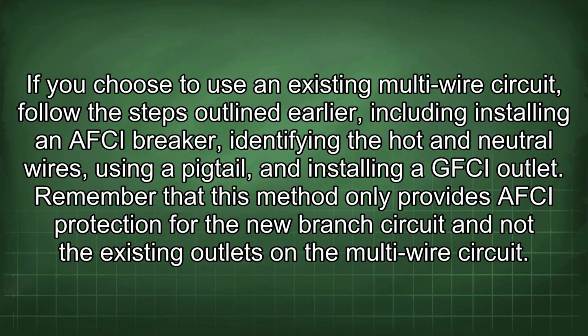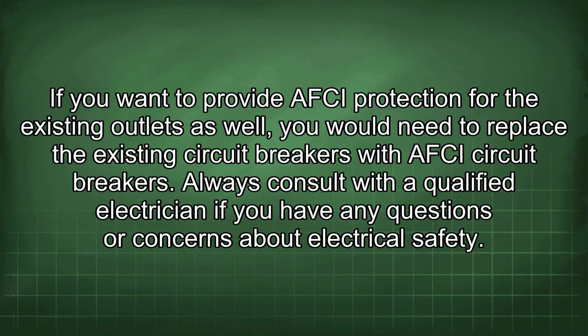If you choose to use an existing multi-wire circuit, follow the steps outlined earlier, including installing an AFCI breaker, identifying the hot and neutral wires, using a pigtail, and installing a GFCI outlet. Remember that this method only provides AFCI protection for the new branch circuit and not the existing outlets in the multi-wire circuit. If you want to provide AFCI protection for the existing outlets as well, you would need to replace the existing circuit breakers with AFCI circuit breakers.